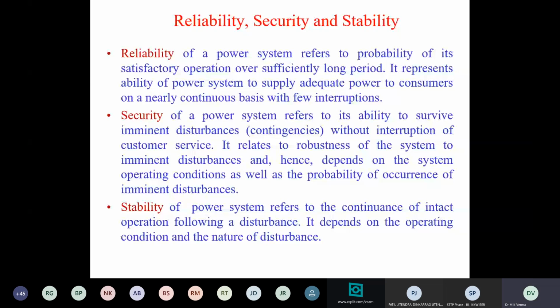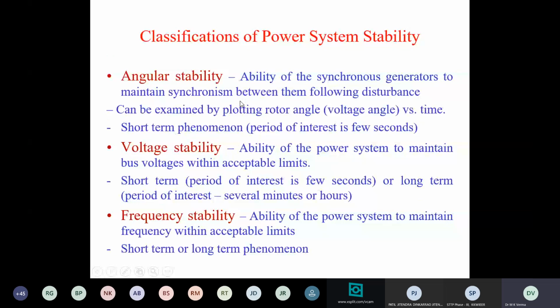Then power system stability can be classified into three types. One is angular stability. Angular stability is the ability of synchronous generators to maintain synchrony following a disturbance. Now, why is it called angular stability? Because this ability to maintain synchrony is obtained by plotting rotor angle delta versus time. So, this ability to maintain synchrony is related to the angular position of the rotor with respect to a synchronously rotating reference. And so, we can plot this rotor angle, the angle of voltage also, with some approximation, versus time. And you see how the behavior is, bounded or unbounded. This is a short-term phenomenon. Whatever happens will happen in a few seconds. Angular stability is a short-term phenomenon.